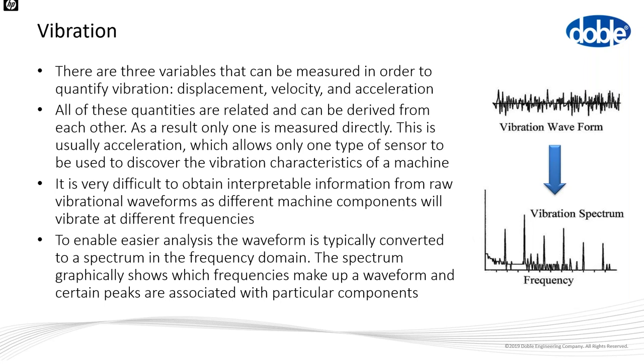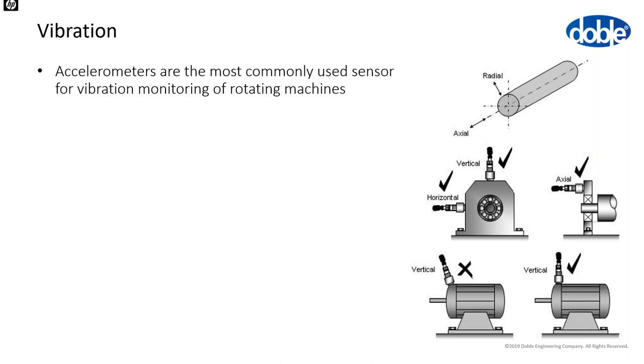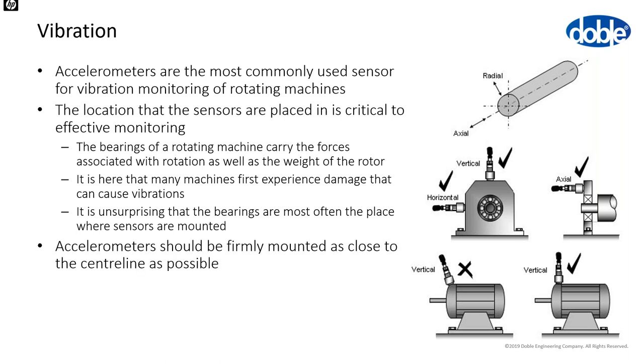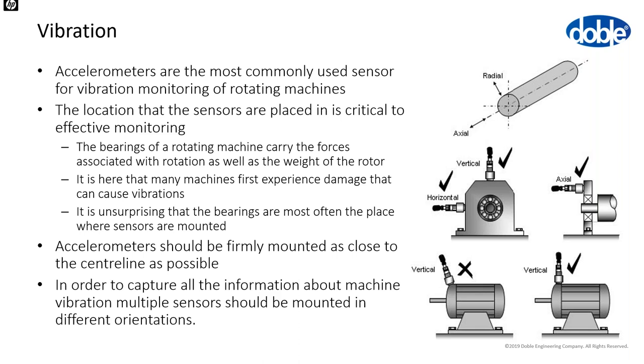Accelerometers are the most commonly used sensor, and sensor location is critical for effective vibration monitoring. Bearings carry forces from rotation as well as the rotor's weight, and this is where most machines experience damage causing vibration. Vibration accelerometers are therefore typically placed on bearings, mounted firmly as close to the centreline as possible. To capture all information about a rotating machine, multiple vibration sensors should be mounted in different orientations, as illustrated in the diagram.